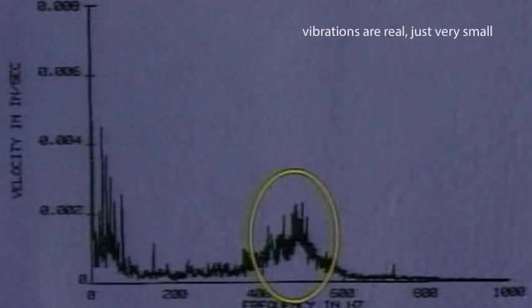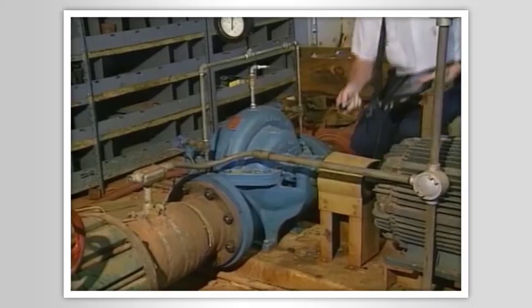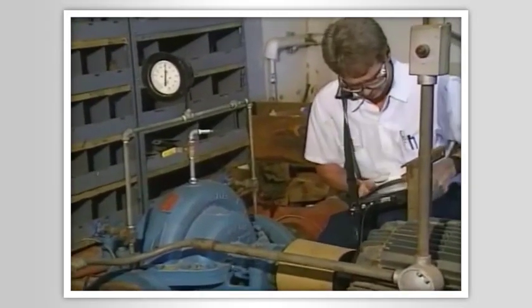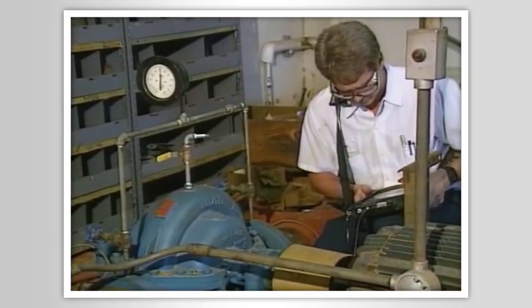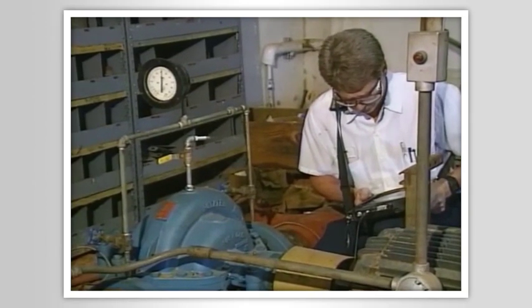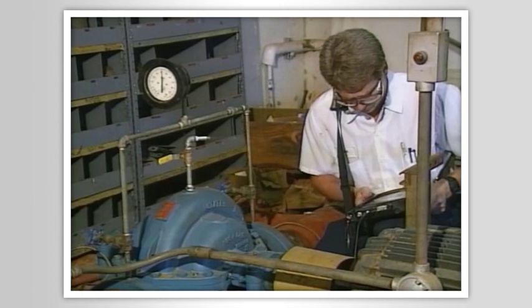A number that certainly seems consistent with the peaks around 500 hertz in the frequency domain. These vibrations are real. They're just very small. This probably is a process vibration. The pump is running so smoothly, the vibration probe may be picking up traveling frequencies through the pedestal, or it may be that we're seeing minor surges in the liquid supply.